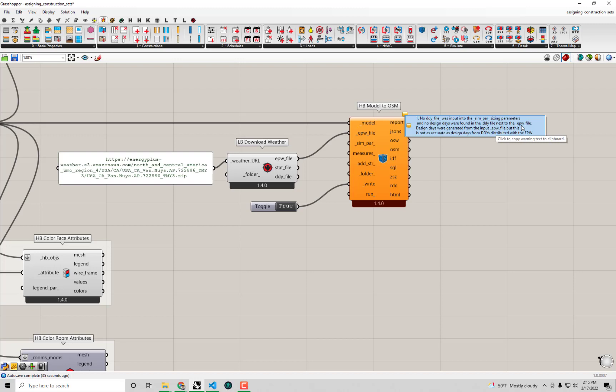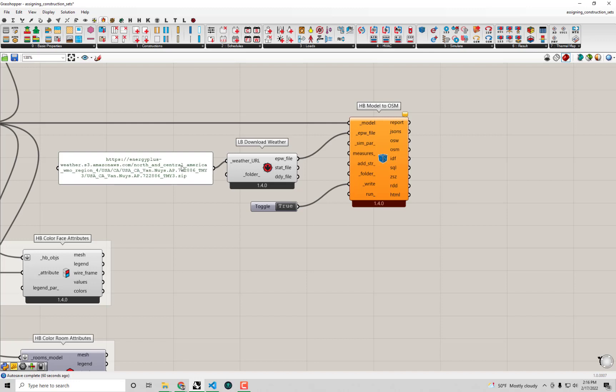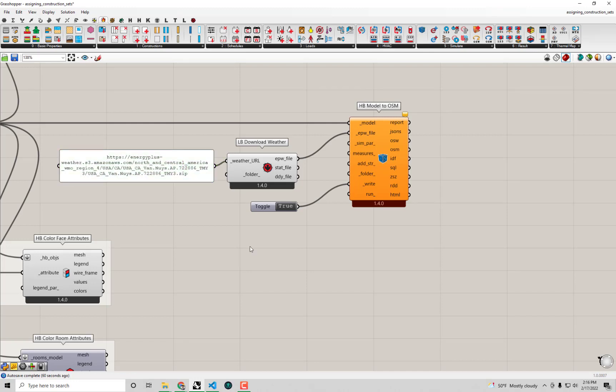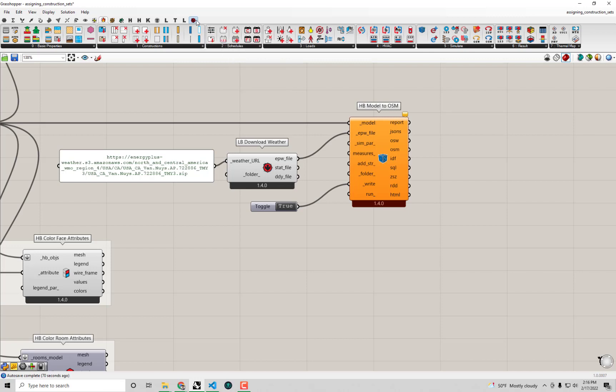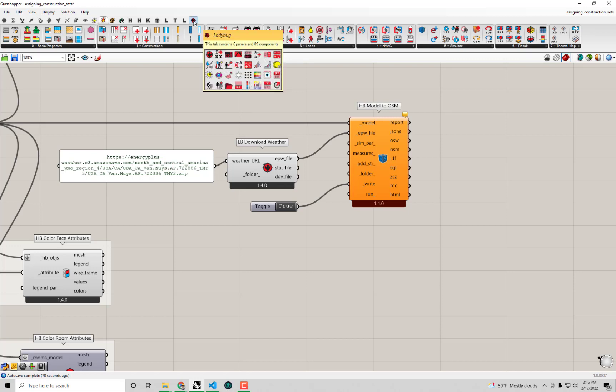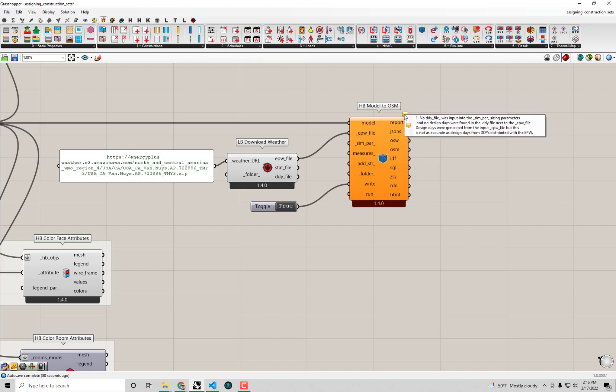We get a message telling us there is no DDY file input to simulation parameters, and no DDY file next to the EPW file. Essentially it sounds like our weather file doesn't quite have all the information we might want for the most accurate energy model. I know there are a few different weather files near our location from the EPW map, so I'll try a different EPW to see if it will make this warning go away. Importantly, just because you get a warning doesn't mean your simulation is wrong or can't be executed — it's just an FYI.